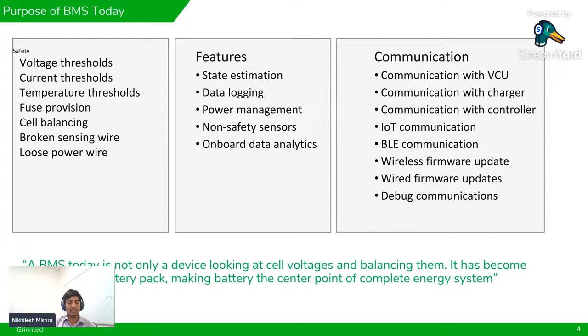Present-generation smart BMS, not all, but really good quality ones, and we do that at Green Tech, can detect if any wire is loose. It's very important, because if you have a loose wire, the contact won't be great, and because of that loose contact it will start heating or can even arc and catch fire. It's possible. So really good quality BMS will have a feature to know if any wire, bolt, or ring terminal is loose. It's not easy, and you won't do it at every point, but at the most important points you can add that feature to know if something is wrong.